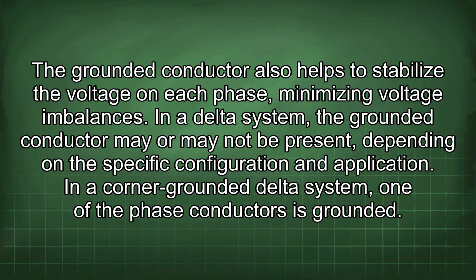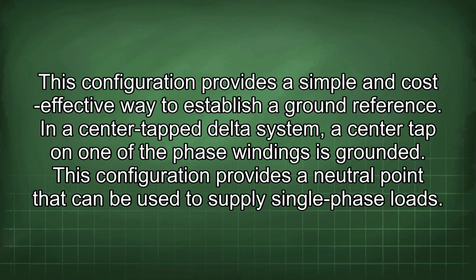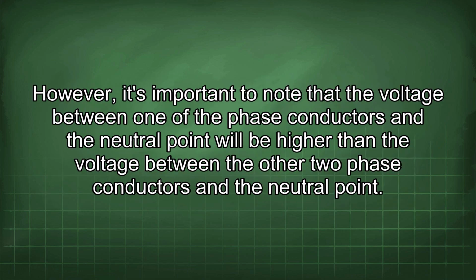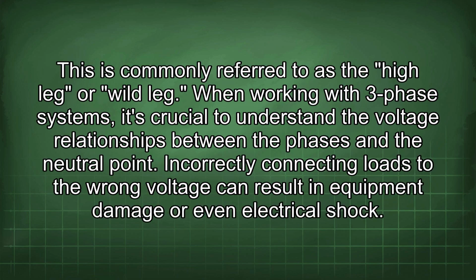In a corner-grounded Delta system, one of the phase conductors is grounded. This configuration provides a simple and cost-effective way to establish a ground reference. In a center-tapped Delta system, a center tap on one of the phase windings is grounded. This configuration provides a neutral point that can be used to supply single-phase loads. However, it's important to note that the voltage between one of the phase conductors and the neutral point will be higher than the voltage between the other two phase conductors and the neutral point. This is commonly referred to as the high leg or wild leg.